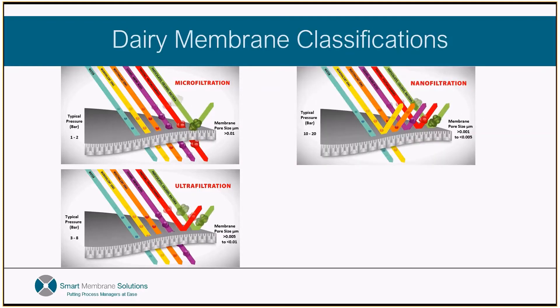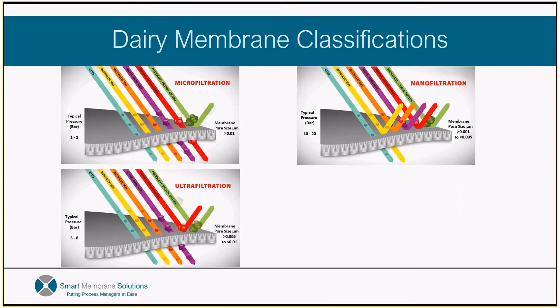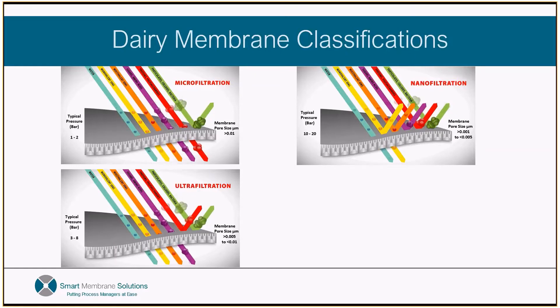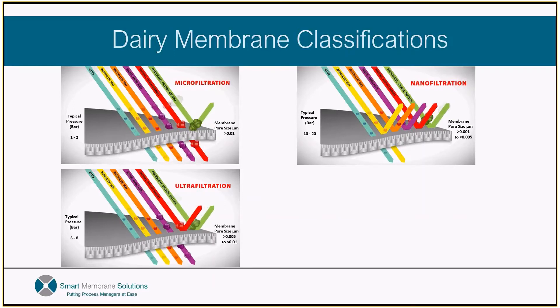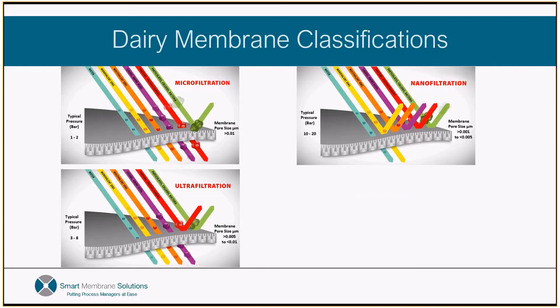Nanofiltration has a smaller pore structure again than UF and can also reject multivalent ions such as calcium and magnesium, whilst having much lower rejection of the monovalent ions such as sodium chloride. NF is often used for desalting or partially demineralising some dairy streams, as well as for purification and colour removal of recovered alkali chemical streams for chemical reuse.